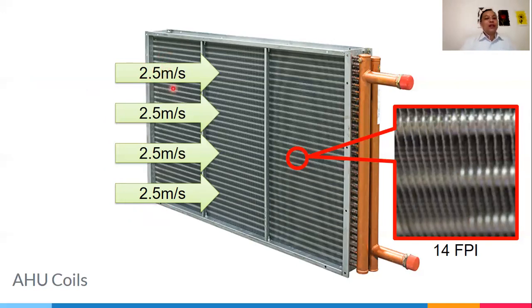However, if you go with lower velocity, yes, you will get better or more efficient heat transfer, but your AHU size will be much bigger. If you want your AHU size to be smaller, you will have a faster velocity, but your heat transfer would not be efficient. So the manufacturers, looking for the middle ground, looking for the most efficient number, determined that at 2.5 meters per second, your AHU will be an optimal size, and you will still have an efficient heat transfer from your air to your water.